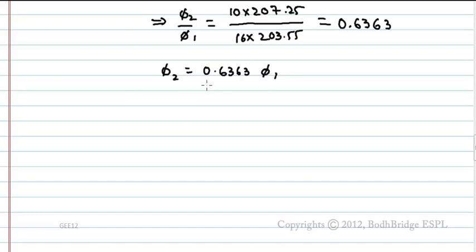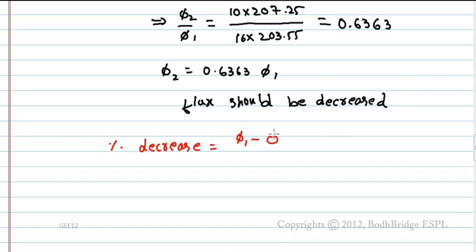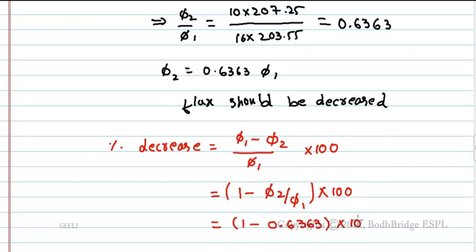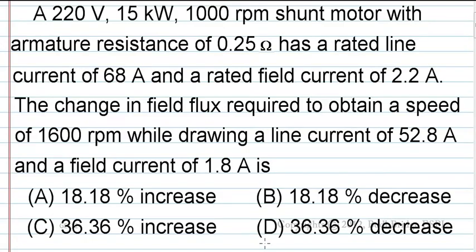From this, it is evident that flux should be decreased. Percentage decrease equals Phi1 minus Phi2 by Phi1 into 100. This equals 1 minus Phi2 by Phi1 into 100, which is 1 minus 0.6363 into 100. This equals 36.36%. So the change in field flux required is Option D, 36.36% decrease.